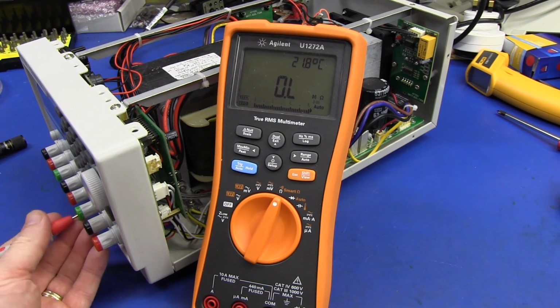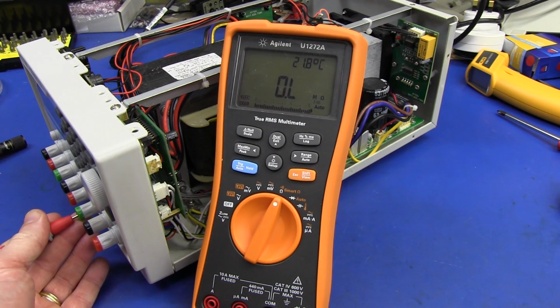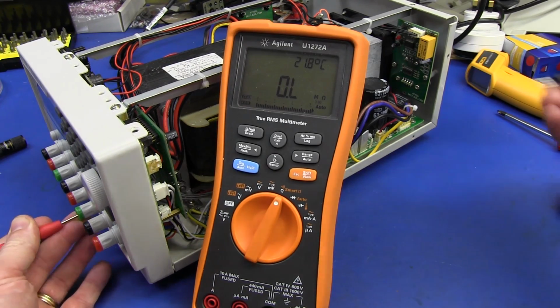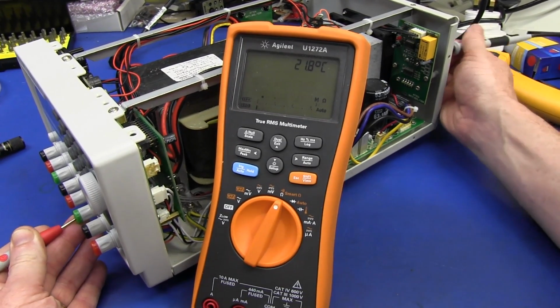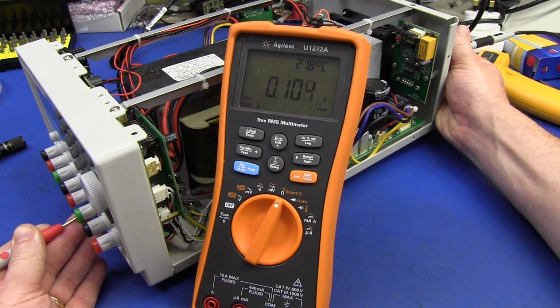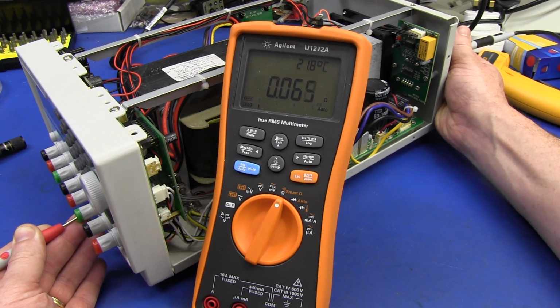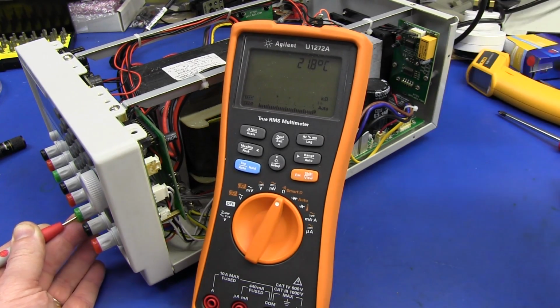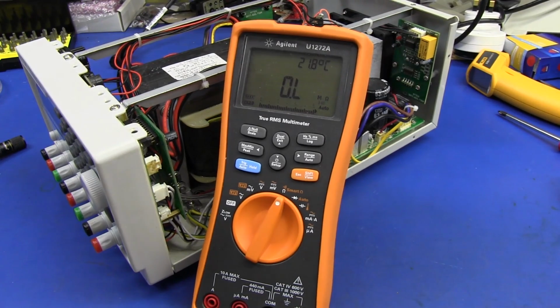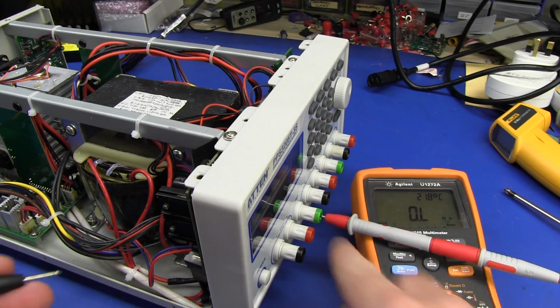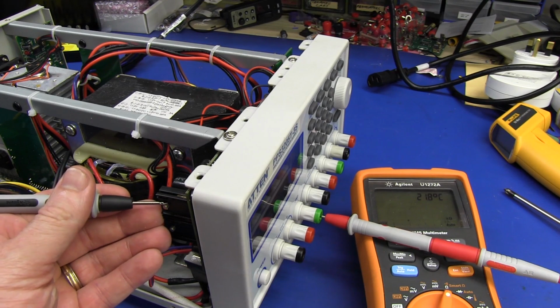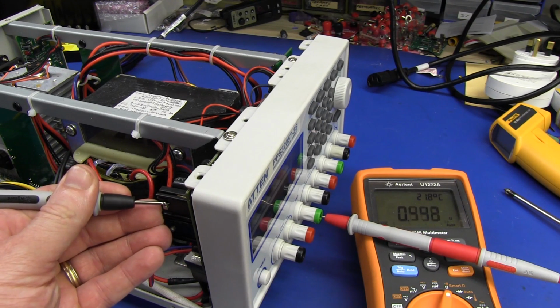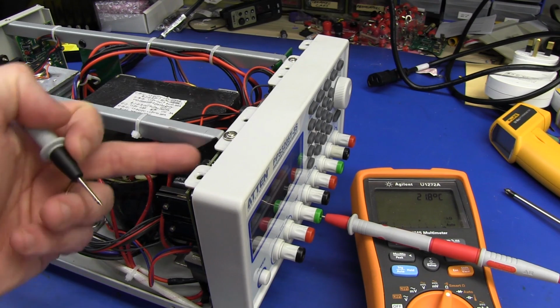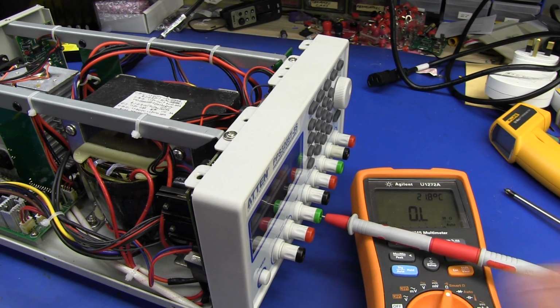And I'll show you that that's the case. Let's go between, no pun intended, the case ground there and the USB input. There we go. That's the negative terminal of the USB input. So they're ground referenced, and you'll find that the logic board is also ground referenced. And you can see that there. We'll go between earth and the regulator tab there. There we go. The logic board on the front is mains earth referenced, but nothing else is. Of course, the front panel terminals aren't.